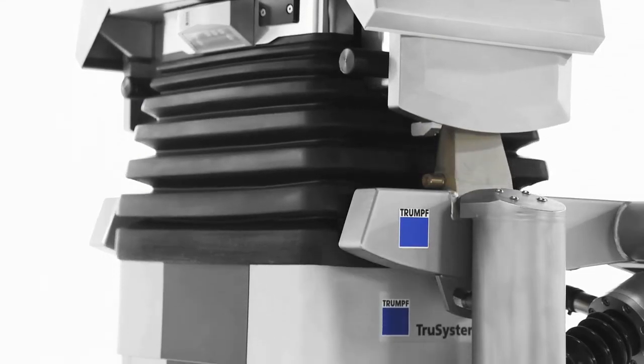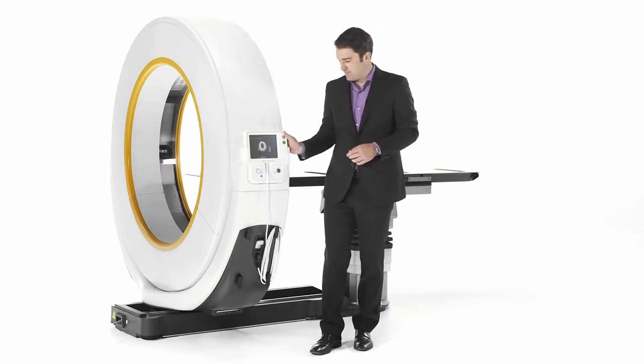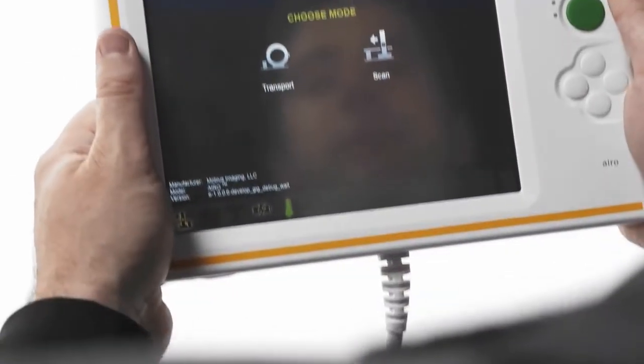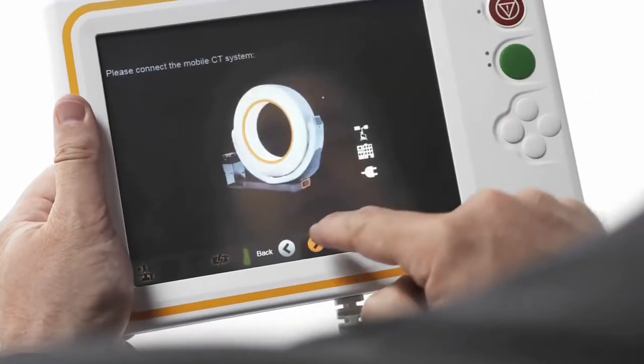The handheld touchscreen pendant is the one central interface for total control of Airo, replacing a separate monitor card. Not only does the pendant control transportation of Airo, it also controls daily calibration and system maintenance, including laser alignment and dose display.